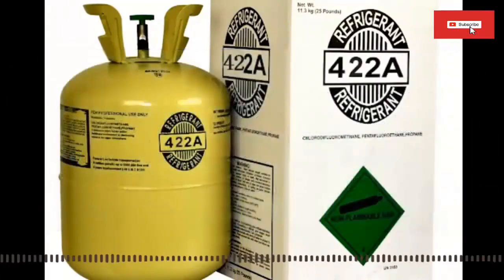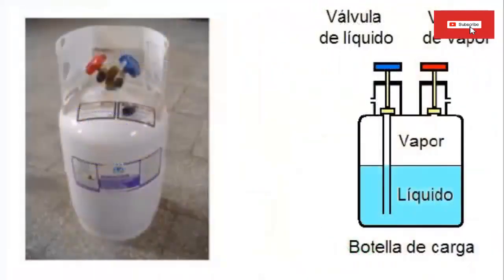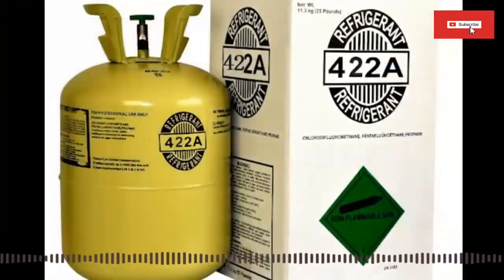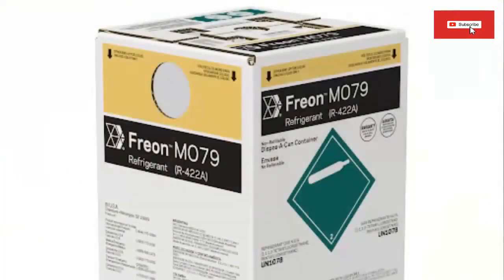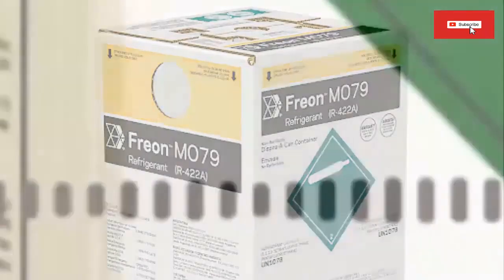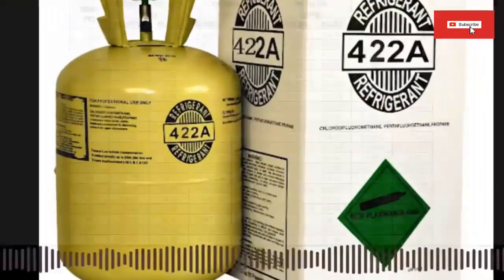12. R422A refrigerant must always be charged in liquid phase from the cylinder. 13. R422A refrigerant is also known as Freon MO79 or ISCEON 79. 14. Field tests show better energy efficiency than R22.